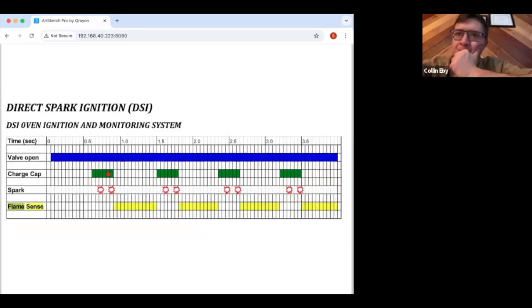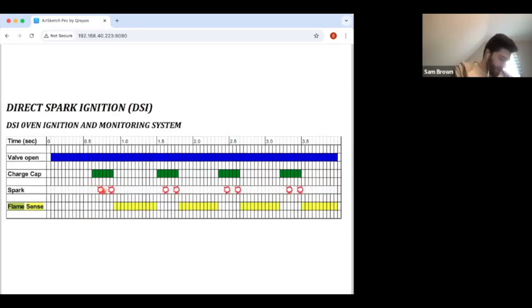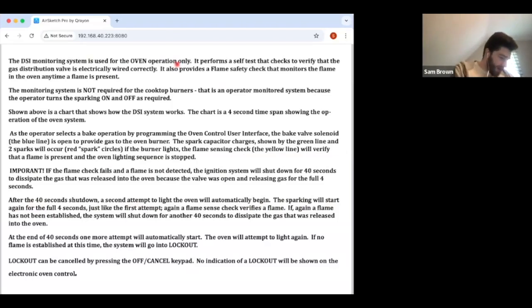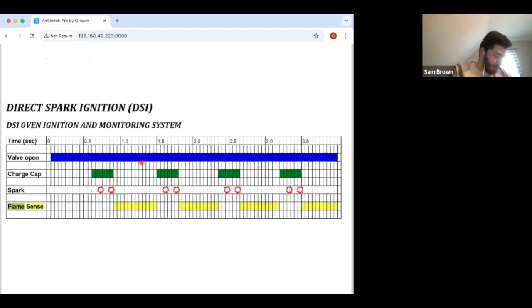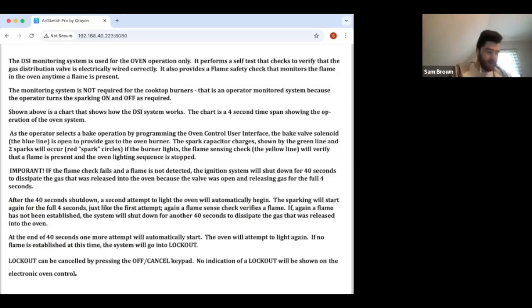Charge up those capacitors, discharge in a spark, and then it looks for that return current. And I'll do that 4 times throughout, so basically 1 time a second. There's a whole breakdown here. I'm going to summarize this for you, but basically this is just saying that that cycle that we just looked at, it'll try this, and if after those 4 seconds it has not sensed that a flame has been established, it will cut off for 40 seconds.